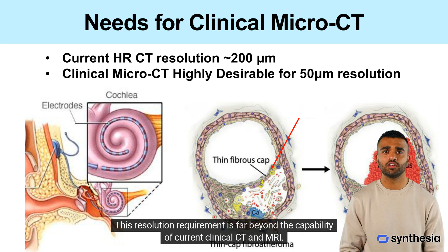To enable clinical micro-CT, we recently proposed a robotic arm-based micro-CT system. We use robotic arms to drive a novel microfocus X-ray tube with 4x more flux than the prior art, and a photon counting detector with fine detector elements and spectral sensitivity to ensure 50 micron spatial resolution. Furthermore, we use interior tomography for ROI imaging to minimize the radiation dose to a patient to a level comparable to that of a regular head CT scan.